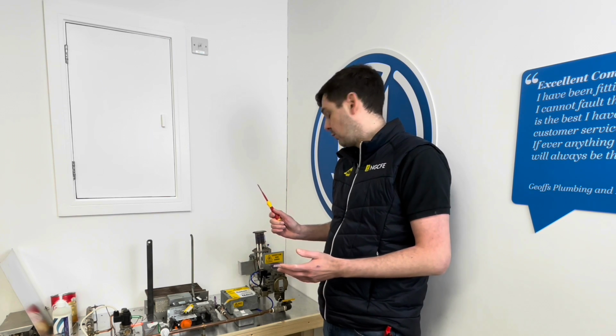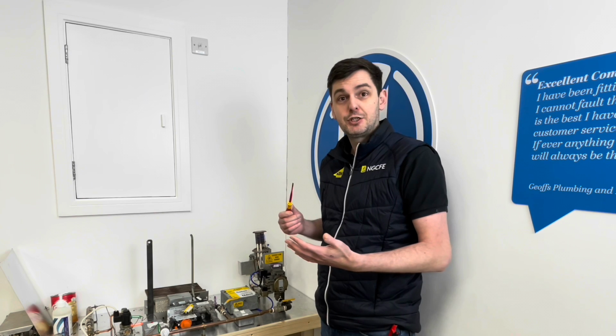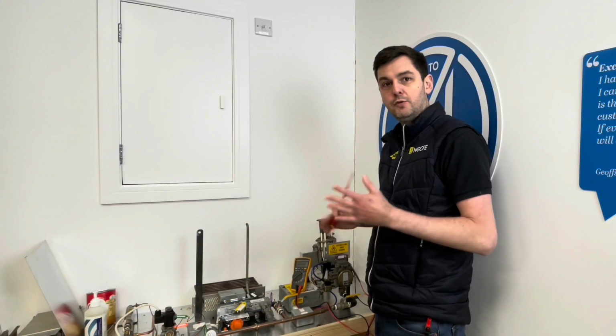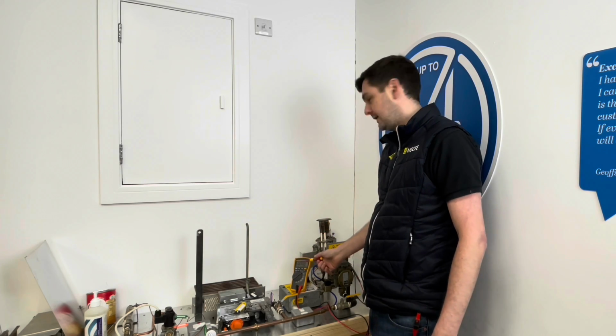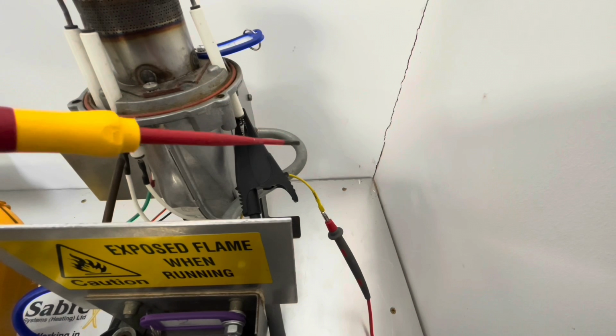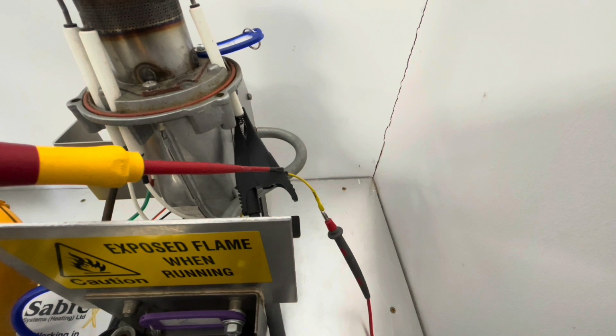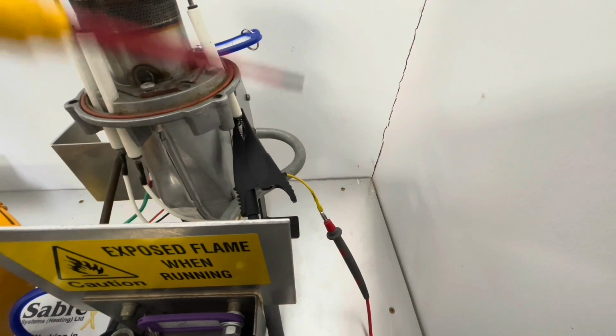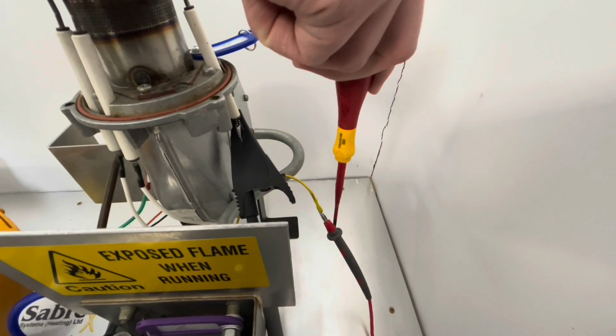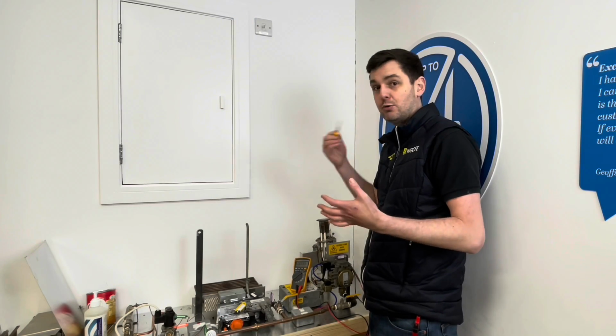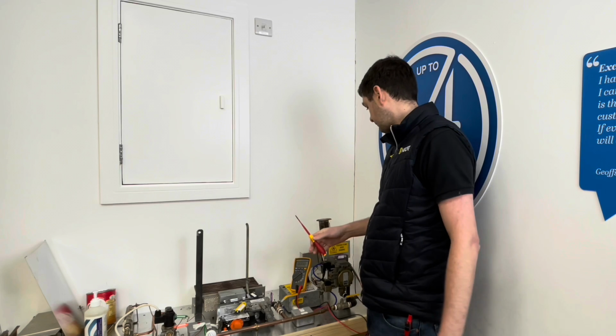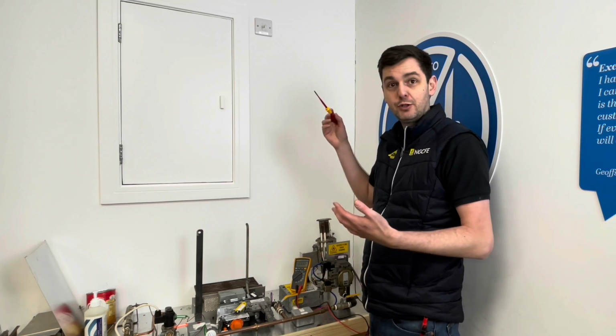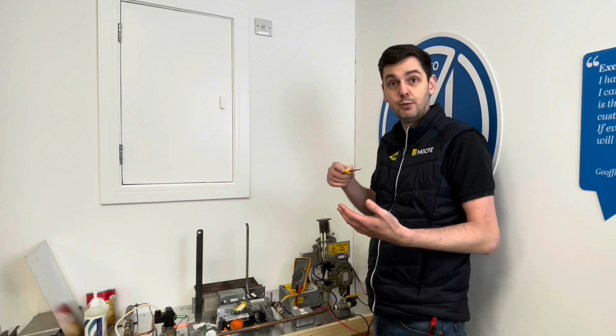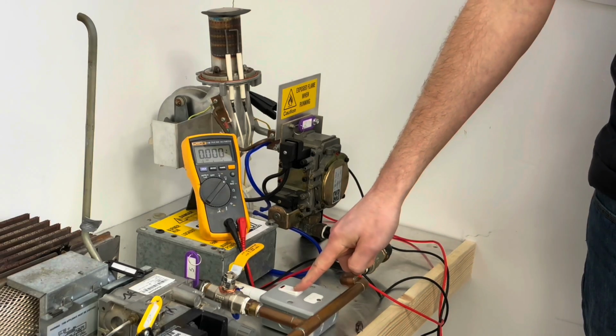So what we're going to do now, just to prove the theory, is attach a multimeter in series, and we're going to measure both the DC current travelling through the flame, and we're also going to measure the microamps. Now, what we've done is connected our multimeter in series. So what that means is we've used a crocodile clip on one of the probes, and we've connected that to the bottom of the rectification probe. And we've also connected our red cable to the rectification lead. So all we've done is basically linked out the rectification probe and the lead. And what this is going to do is measure the voltage in DC going back to the board. So let's try it on.